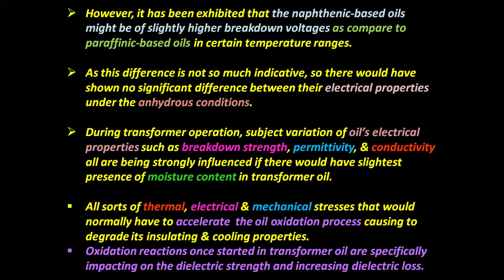During transformer operation, variations of the oil's electrical properties such as breakdown strength, permittivity, and conductivity are all strongly influenced by even the slightest presence of moisture in the transformer oil. All sorts of thermal, electrical, and mechanical stresses normally accelerate the oil oxidation process, causing degradation of its insulating and cooling properties. Oxidation reactions, once started in transformer oil, especially impact the dielectric strength and increase the dielectric loss. Most important.